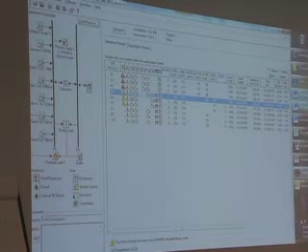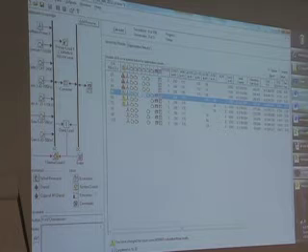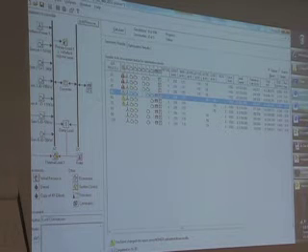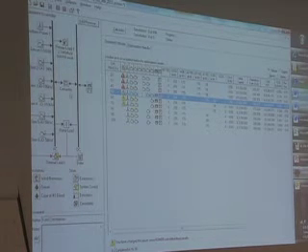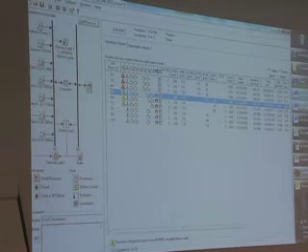The yellow means, okay, you've got some storage, but your instantaneous penetration is high enough that you really need to do some dynamic stability modeling with one of the more detailed models.